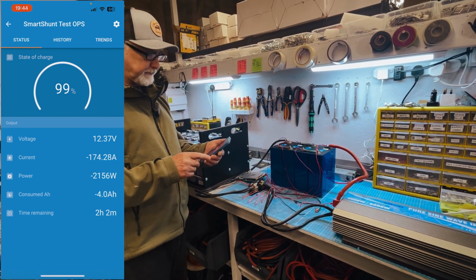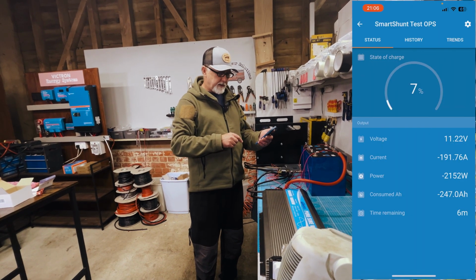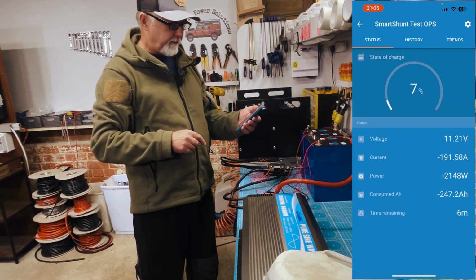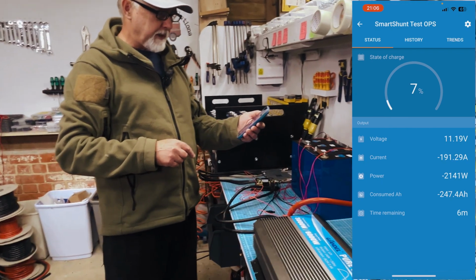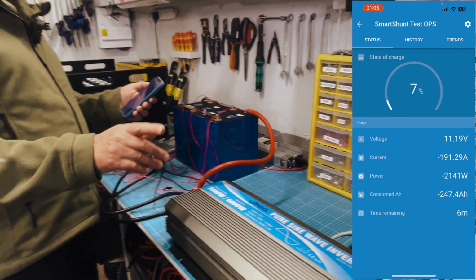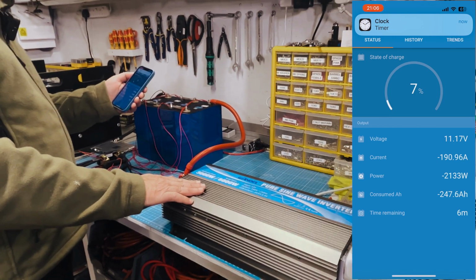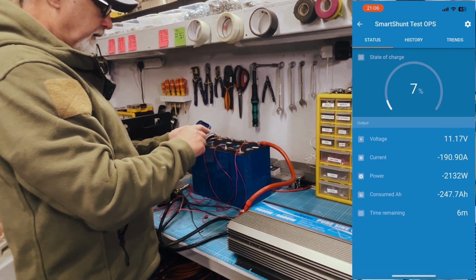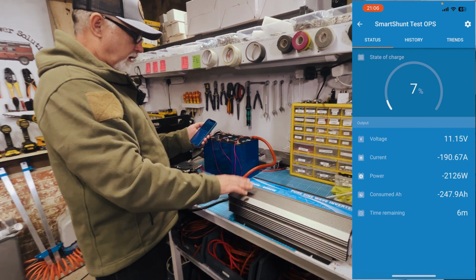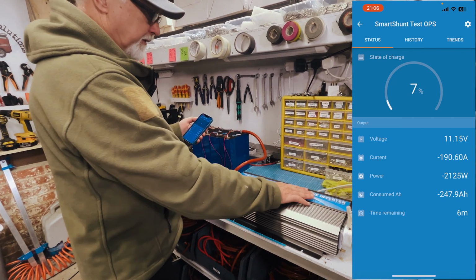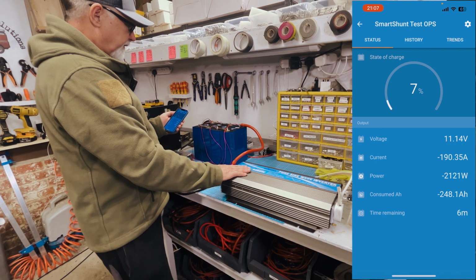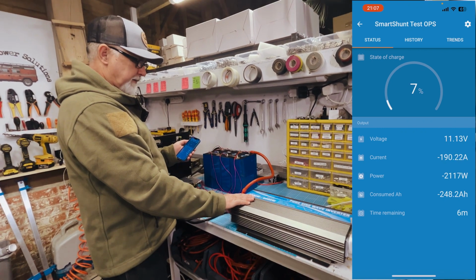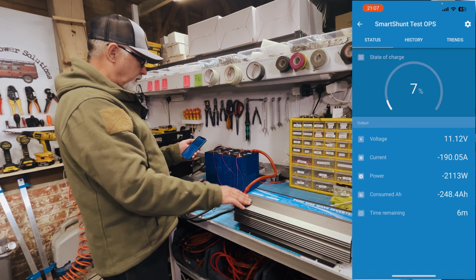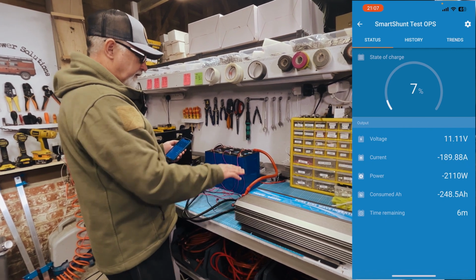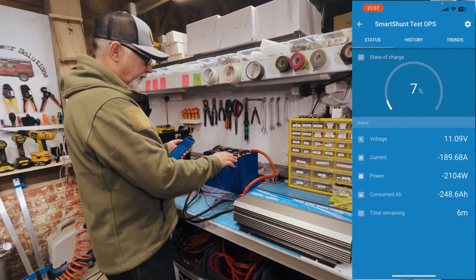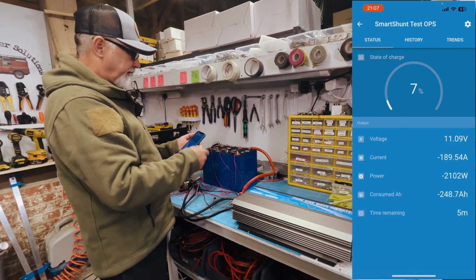So the test is running well. We're approaching 250 amp hours. I'm going to bring this down from roughly 190 amps down to half of that. I'll turn this down just to give this a chance to get as close to its capacity as possible. If I run it at full bore, 190 amps, the cells will reach their cutoff a little bit sooner, so just to be fair on them.